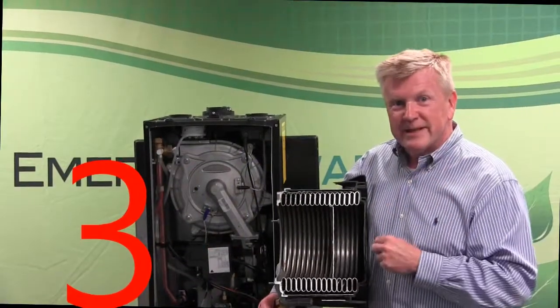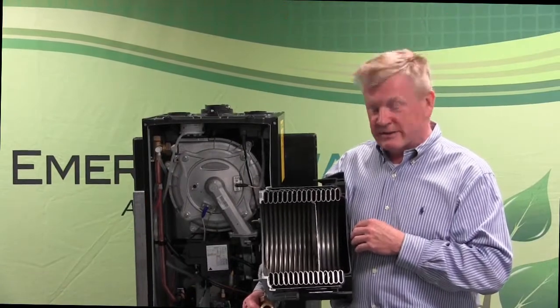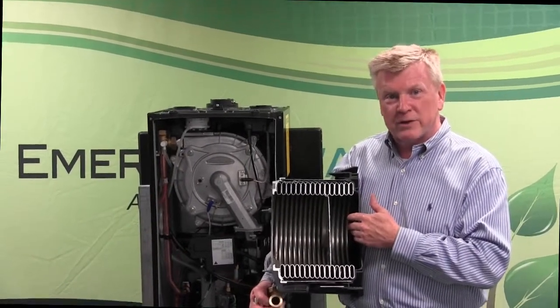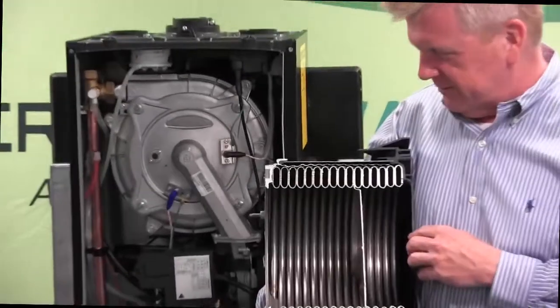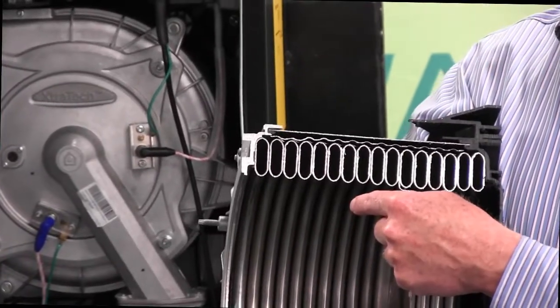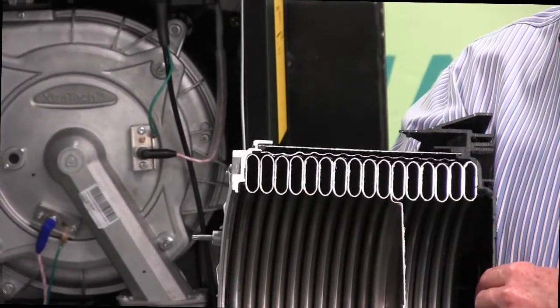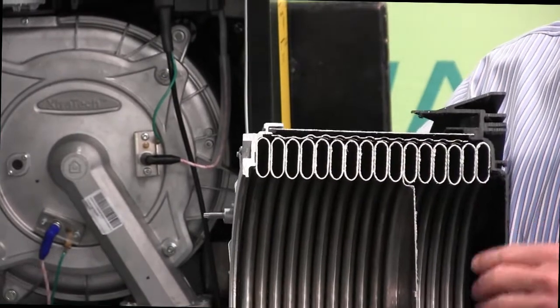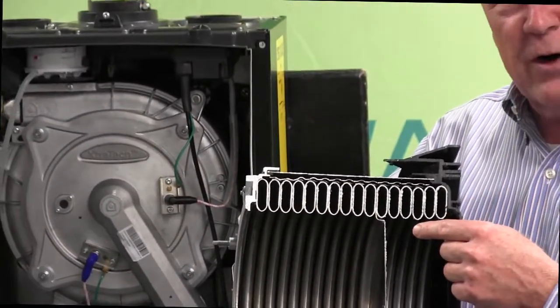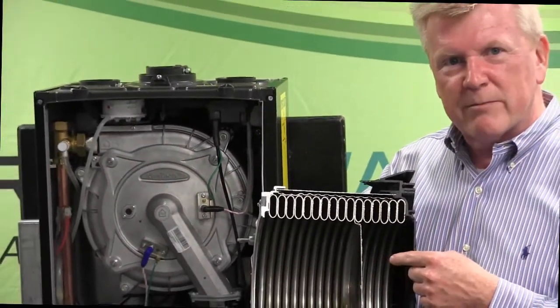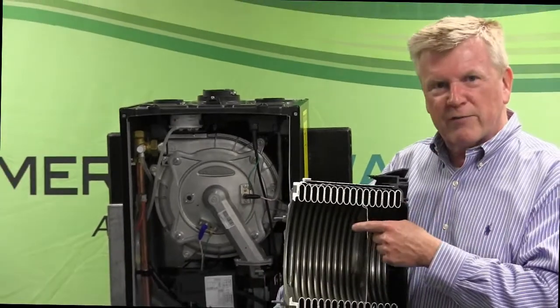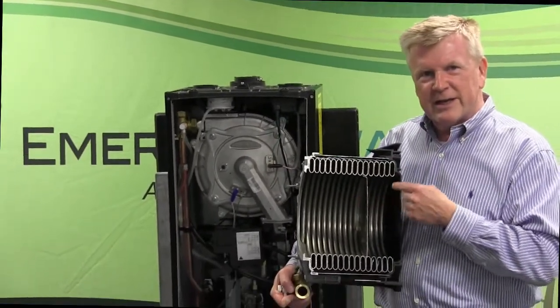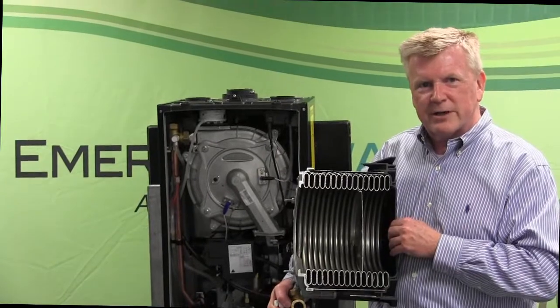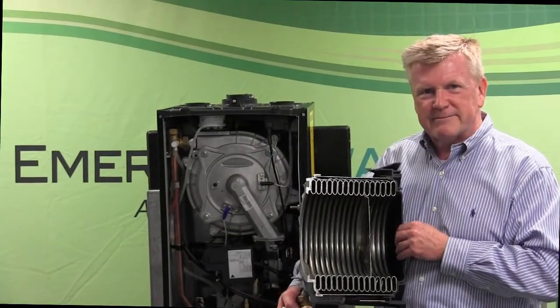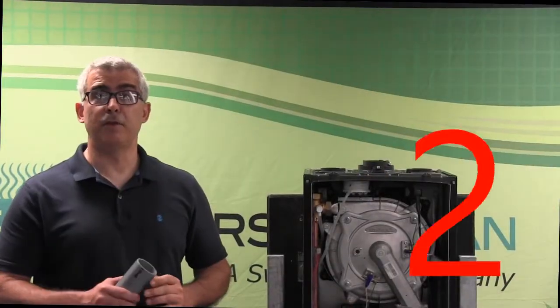Number 3, the Extratech heat exchanger by Ariston. One of the manufactured components, the beating heart of the system. Water tube heat exchanger, 150% larger design than our leading competitors. What does that do for you? It lowers the pressure drop, smaller pumps, better flow, better heat exchange, less likely for the system to clog up on you. Great design.